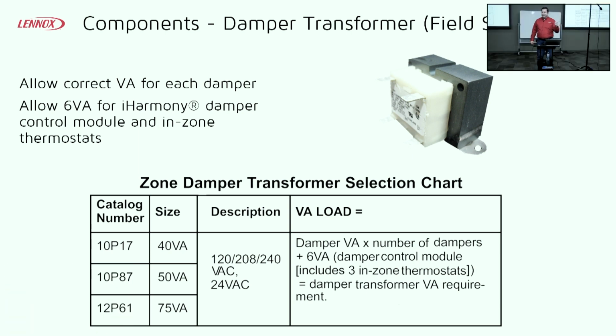We'll tell you technically, you can install these without one. I always tell folks, always install one of these. It just makes things a whole lot simpler, because essentially what this transformer is going to do, it's going to power the zone board, it's going to power your zone thermostats, and it's going to power your damper modules. Now you can set up the zone control to do all that with the transformer inside the unit. There's a little dip switch on the board, and we'll look at that a little bit later on.